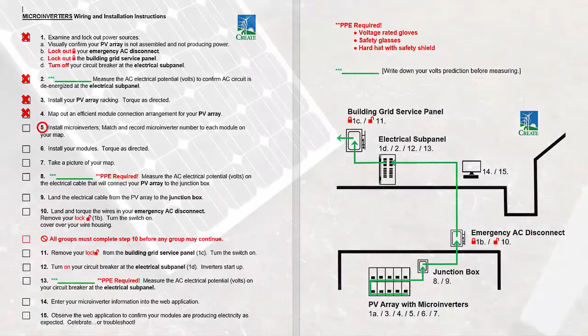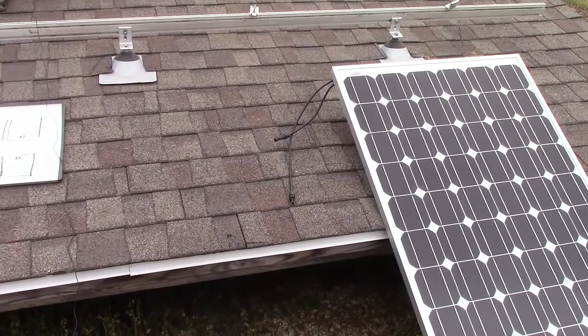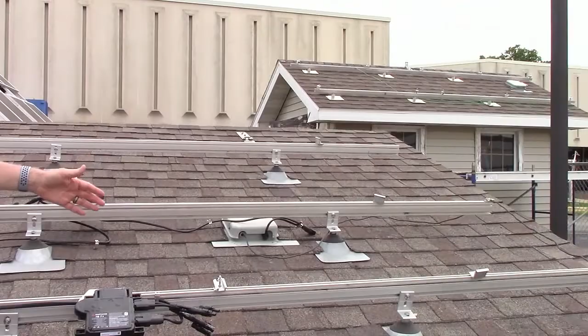Step 5 is to install our microinverters. We will match and record the microinverter number to each module on our map. We've located the microinverters on the rails in locations where they'll be underneath a module, so they'll be protected from the weather, and where we know we'll be able to attach the positive and negative leads from the 2 modules that will connect into each microinverter. Also, we've attached the AC cable that connects all the microinverters together and connects into the building's electrical system. We've attached that to the microinverters and secured it to the rails.